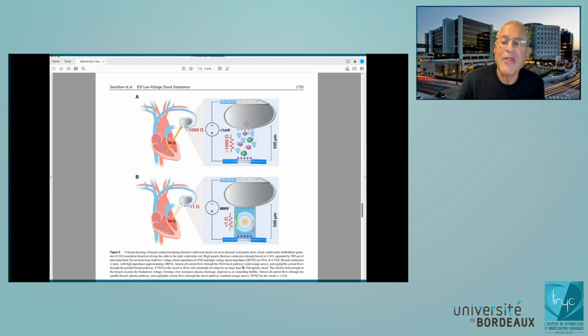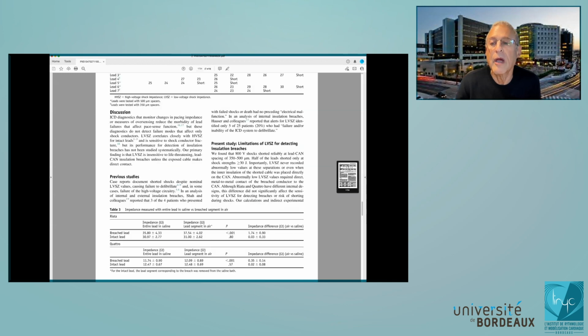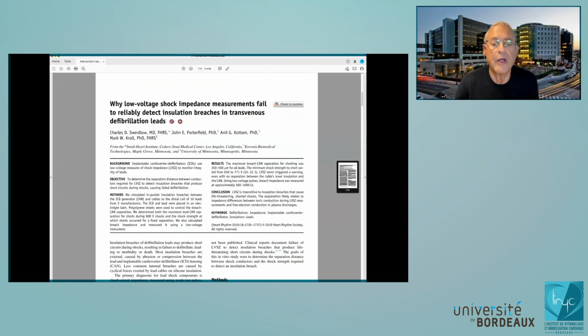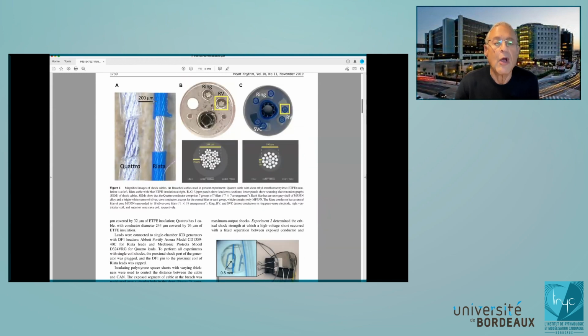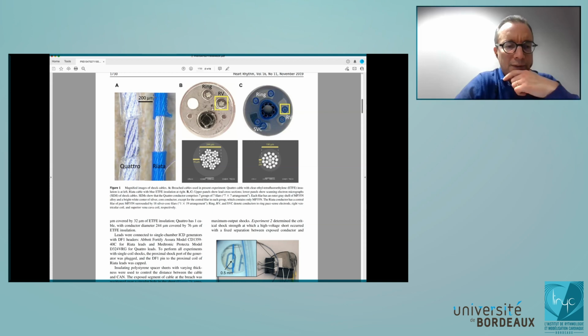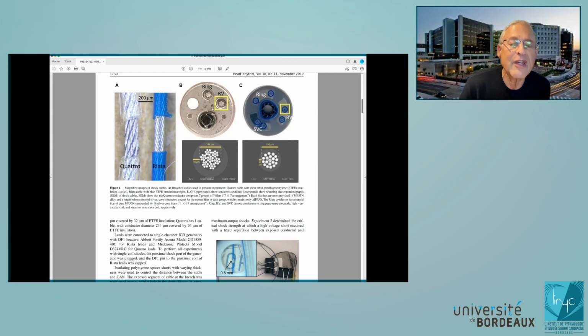And so if you have 1,000 ohm impedance, and even if you put the lead down right on the can, what actually touches the can, you can see, is the plastic right here. Does that make sense? Maybe I can go here. You can see my cursor, right? If we lay this right on the can, what'll actually happen is the plastic touches the can here, the plastic touches the can here. We have a huge insulation breach, but there's a little interstitial fluid between that and the can. So it really has to actually just be bending up against the can.